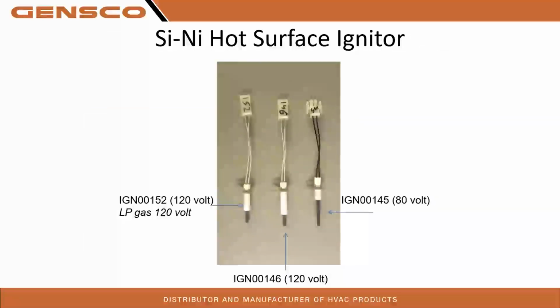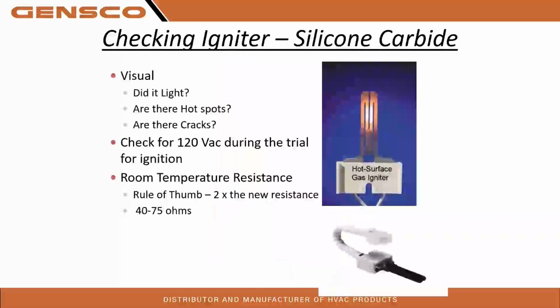So when we look at them here, we have the nitride igniters that we use, one being 80 volt. See how this one's round, so it can throw you off a little bit. It's not always true. The 80 volt 145 is 80 volt here. It's a real long silicon nitride. Then we have the two shorter versions, 120 volt LP gas, and then we have the 120 volt 146, which is basically the same version of this with a longer isolator on it. Okay, so carbide. This is obviously another large brand, Bryant Carrier style igniter.